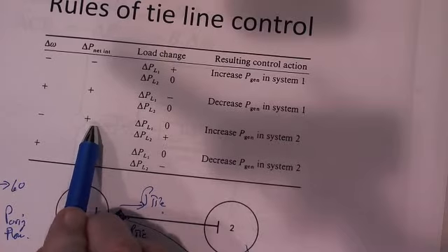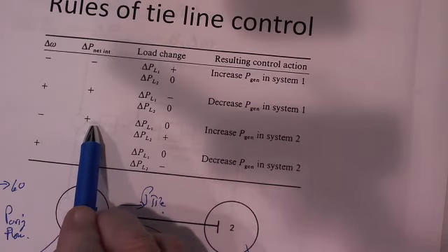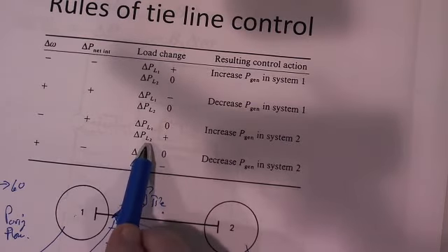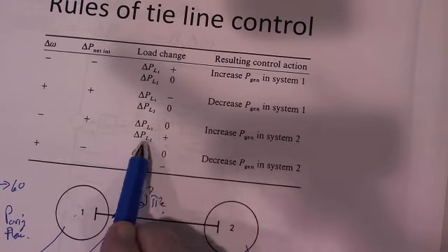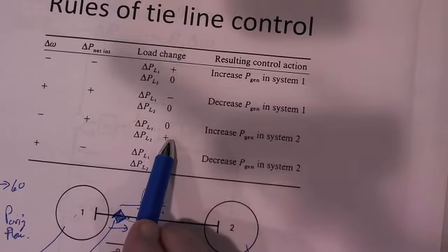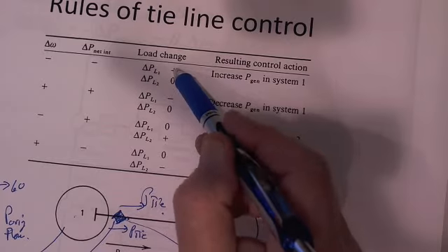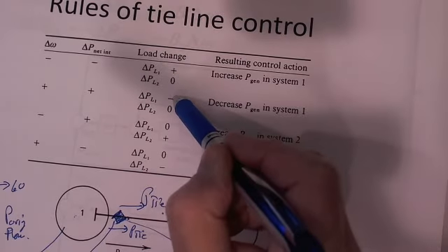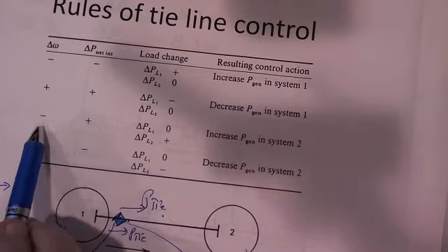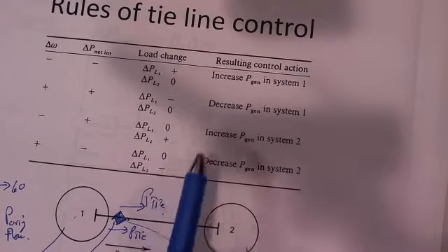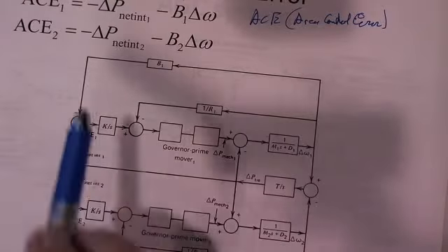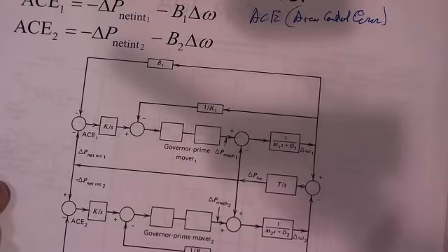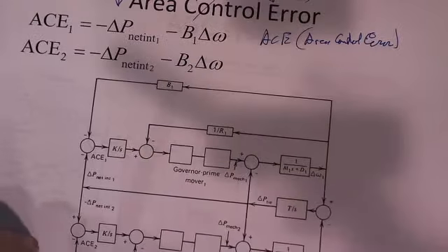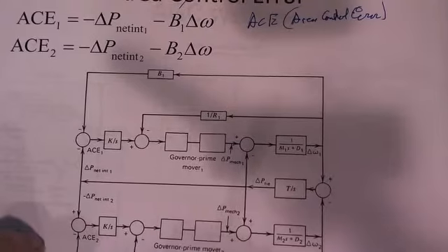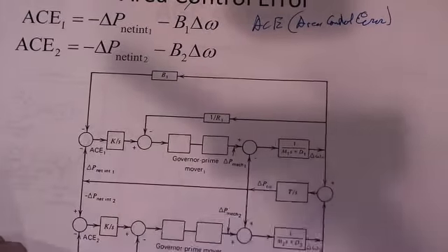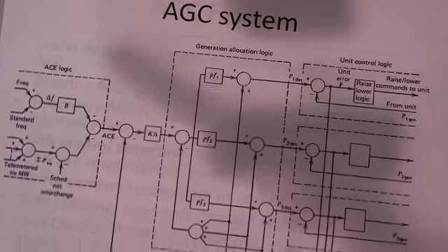If one was negative and one was positive, then we know that the load went up in L2. Remember, up here the load went up or down in area 1 and nothing happened in area 2. When they're opposite, down here, it was all in L2. So this signal will be 0 for one of the control areas and non-zero for the other, and it tells which of the control areas ought to do this.